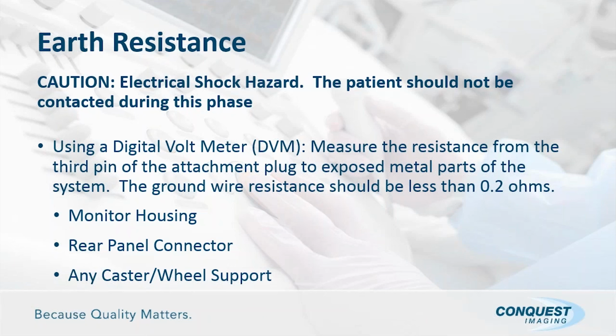They changed it to 0.5 ohms because they wanted to match the international standard, IEC 60601, which was 0.5 ohms. So they went ahead and made the change to increase the ground resistance, but in either case, it should be less than 0.5 in all circumstances. And they want you to check it in more than one place, though. They don't say just any place.